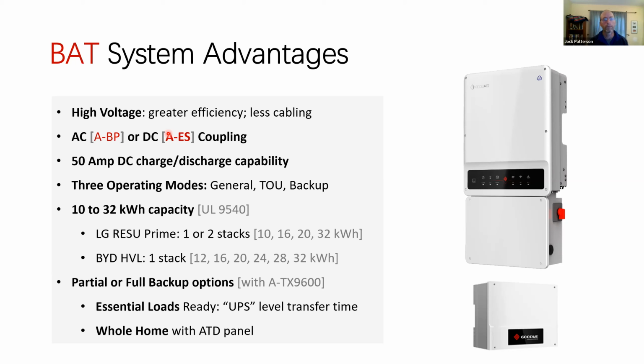If you're trying to do an inverter outside of a garage and then the battery on the inside because of operating environment, you're not supposed to have the battery in that cold environment. Try running 4-aught cable through walls. It's much easier using number 6 and number 8 THHN because you're using high voltage batteries. So another benefit of using high voltage batteries is distancing the inverter from the battery if necessary. We offer both AC and DC coupling because if you're using a battery only, that's ideal for AC coupling or retrofitting. And then DC coupling is for the hybrid, right? We're going to have the PV and the battery all going through one inverter.